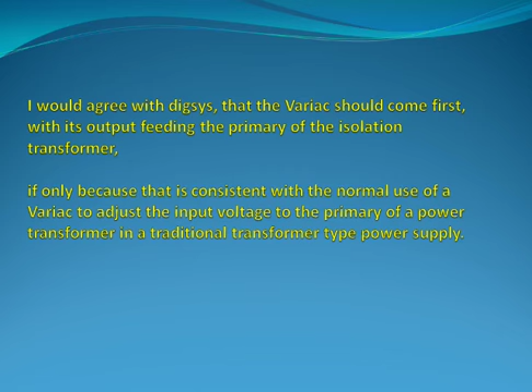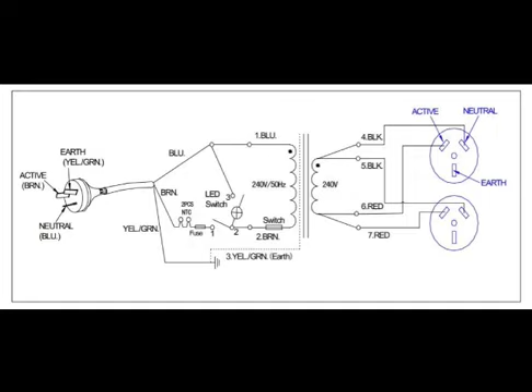Here's a schematic of the internal workings of my isolation transformer. As you can see, on the primary side we've got active, neutral, earth, all connected as they should be. On the output, we've only got active and neutral, and the earth is not connected at all, so it's isolated. Let's go back to the bench, open up the transformer, and visually inspect it to see if that's exactly the case.